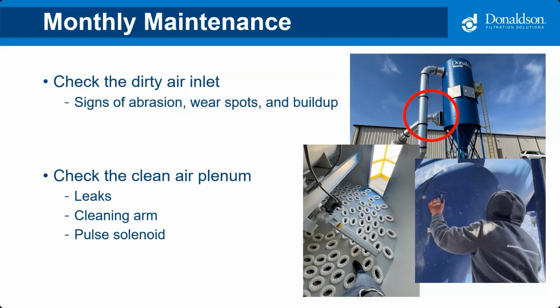We also want to check the clean air side of the dust collector, and that's the two pictures on the bottom. There's a technician removing an access door on the bottom side of a hopper and a bag house, and the picture in the lower left is actually inside the bag house, above the filters, kind of looking down on the bag filters. Again, on the clean side, you want to make sure you're not seeing any leaks in the system, so it should be clean on that side.